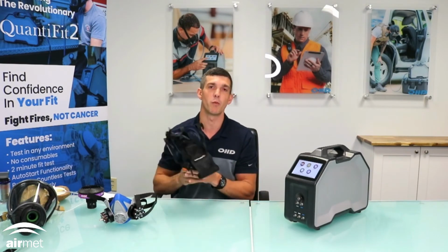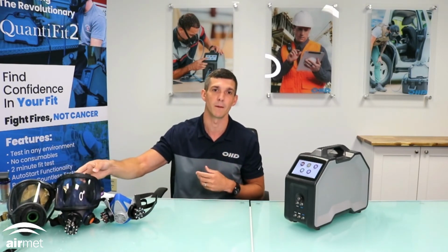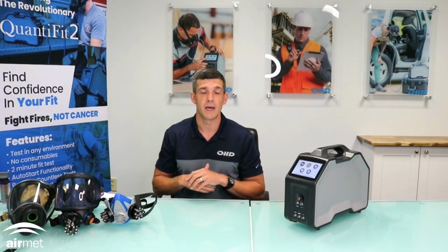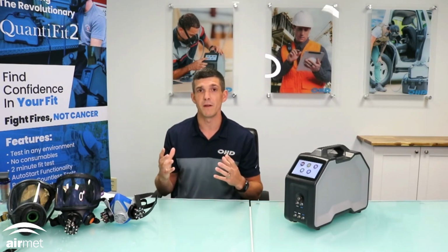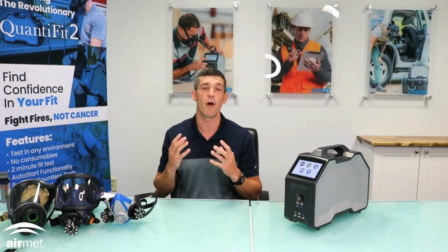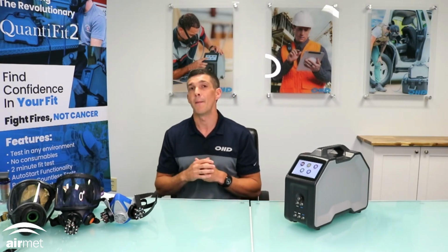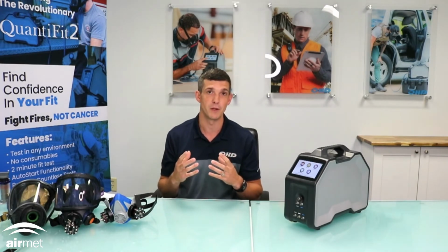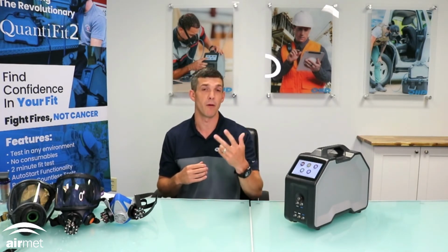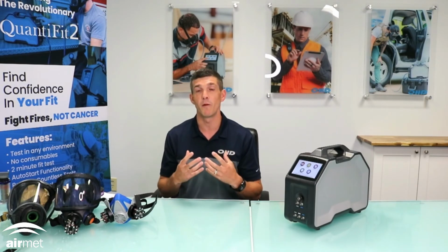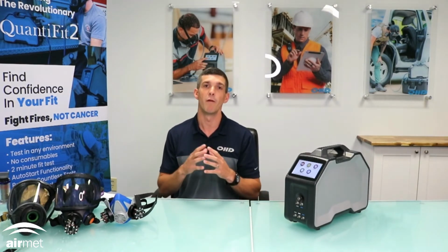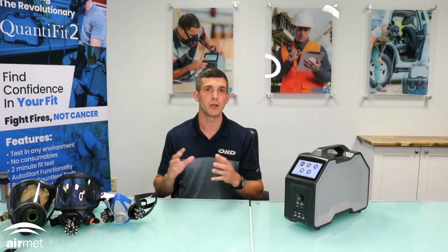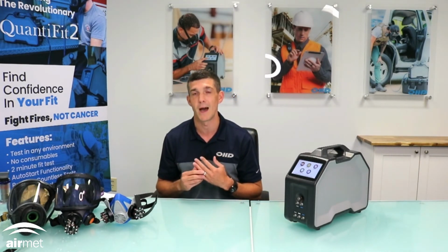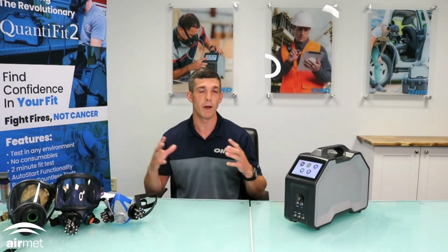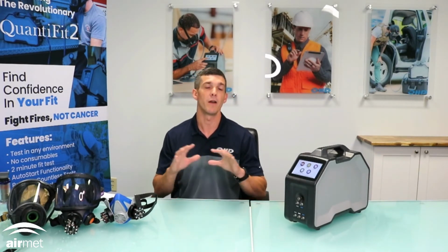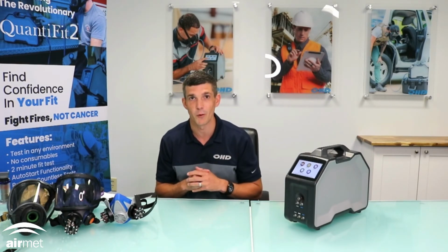So we remove all of those probing requirements and consumables that go into testing. I already mentioned the setup time earlier, and that's another big advantage. The other thing is we don't have to wait for particle purge in the respirator. Some other manufacturers have requirements to do particle purge time. If someone has smoked or been around food and consumed food before fit testing with aerosol methods, they have to wait before they can start a fit test. With controlled negative pressure, we don't have any requirements to do particle purge times or to wait for smokers to wait for 20, 30 minutes before fit testing. None of those requirements are on controlled negative pressure with QuantiFit 2.